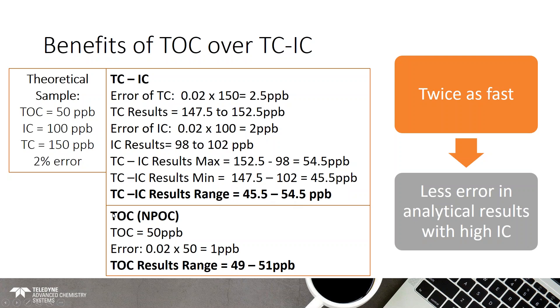With a TOC-direct measurement, you're only doing one measurement, so error is factored in only once. The range is just 49 to 51 ppb — much more precise than TC minus IC. And it's also twice as fast. Some people argue that TC doesn't involve purging, but there's a lot of cleanup between TC and IC measurements, so it really does work out to about twice as fast with TOC.